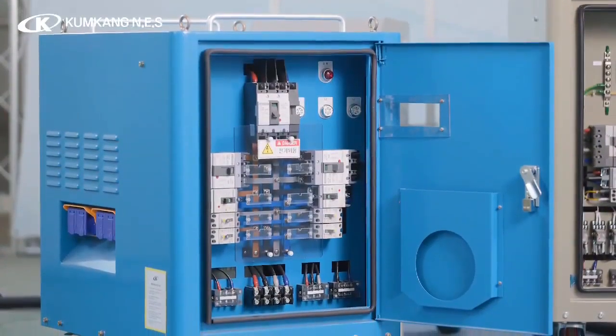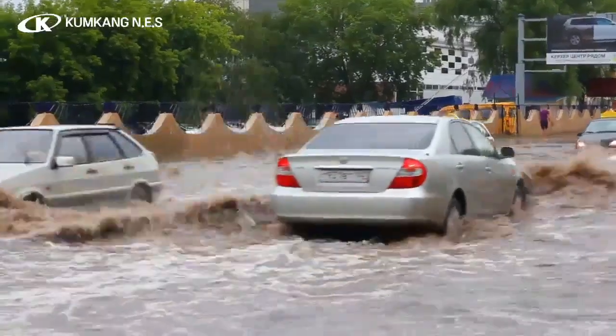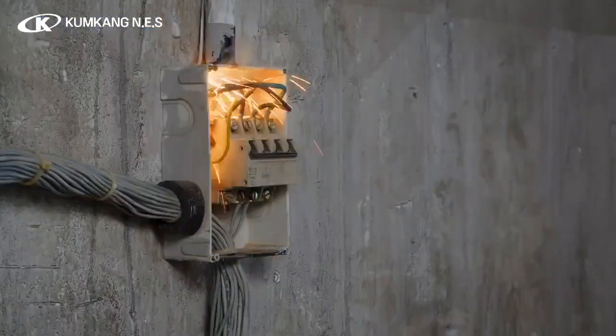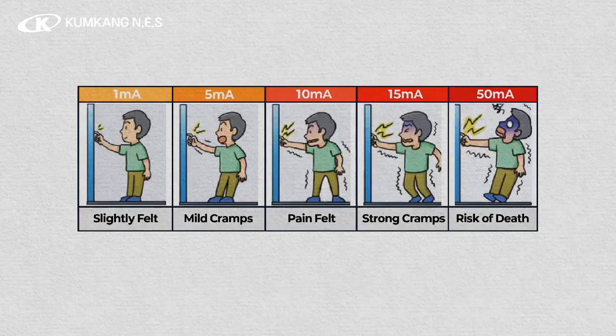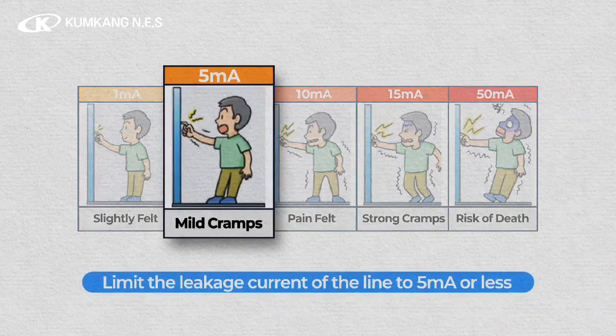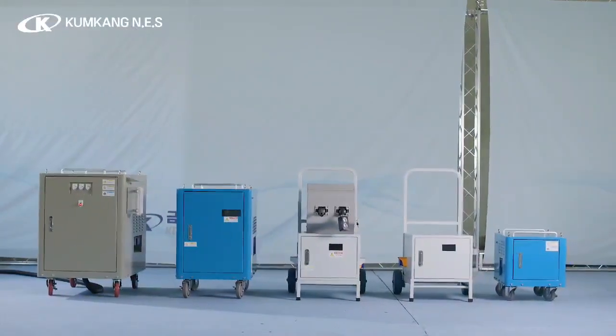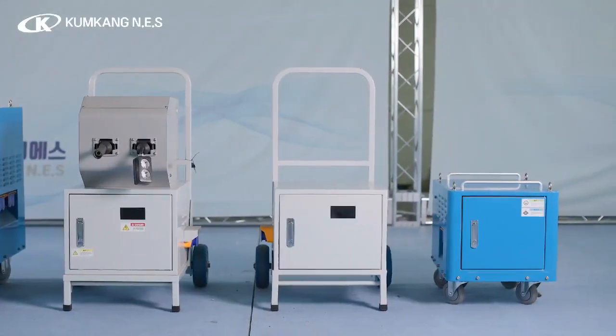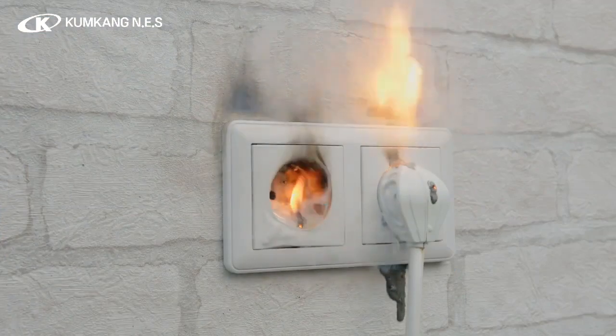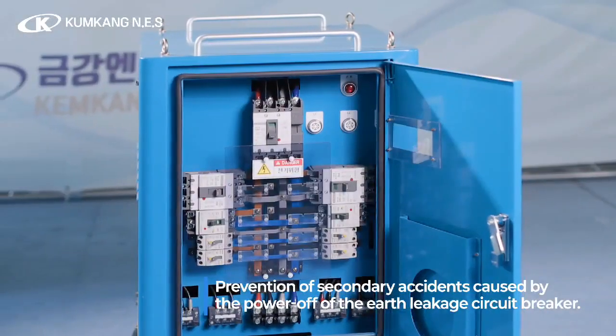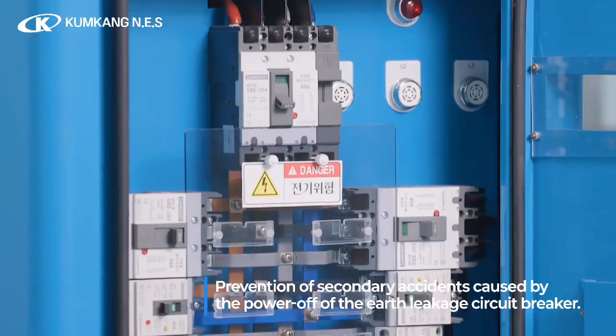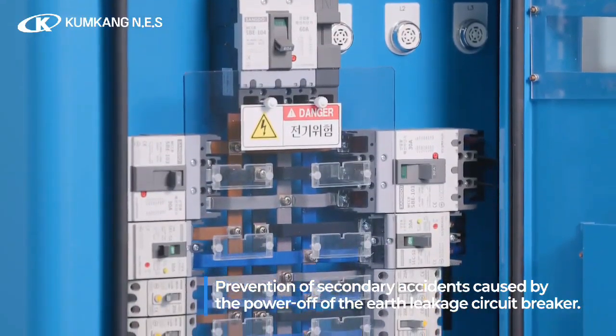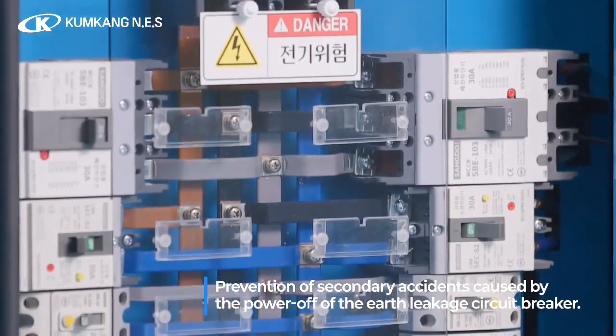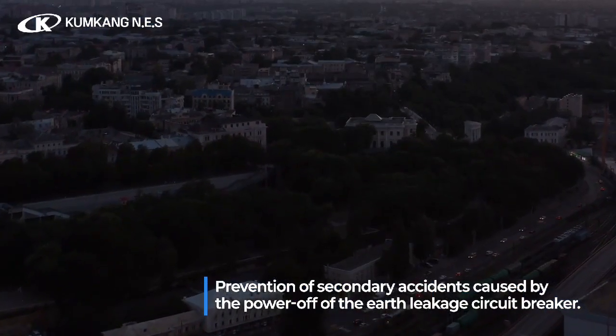The leakage current limiting power supply limits the leakage current occurring in the entire line and load to 5 milliamperes or less in case of electrical faults such as ground faults, leakage, or flooding. It not only prevents electric shock accidents and ensures a stable power supply. Even if an electrical fault occurs, it is impossible to reach the rated sensitivity current of the earth leakage circuit breaker, 30 milliamperes. Therefore, secondary accidents caused by the power off of the earth leakage circuit breaker can be prevented.